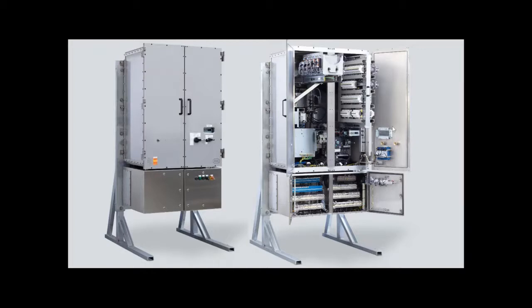Now, to mention an industry trend that I've come across many times: manufacturers will buy an empty enclosure and throw whatever they want into it, and then sell that enclosure, install that enclosure, and we inspectors in the field are stuck with this. And then the end user and the EPC are taken advantage of. Now, if you see anything with a U certificate on an enclosure, that means that enclosure was sold from the likes of, let's say, R.Stahl to another manufacturer. That other manufacturer, it is their responsibility. They are legally responsible for whatever they put in there. They must then have it tested and certified. So be aware of that.